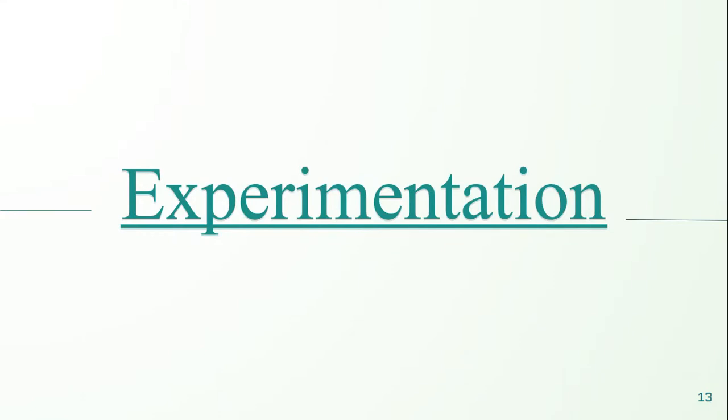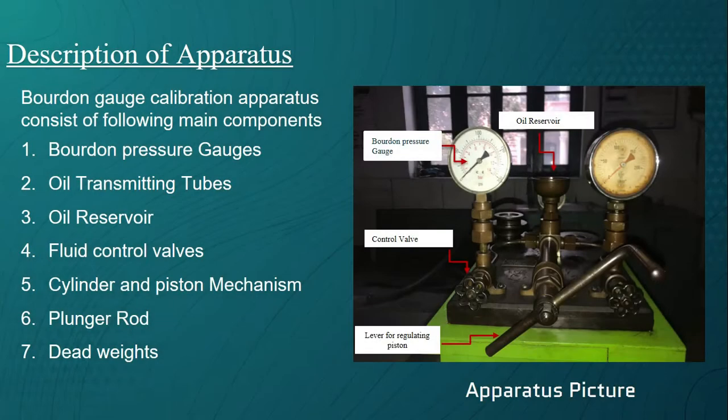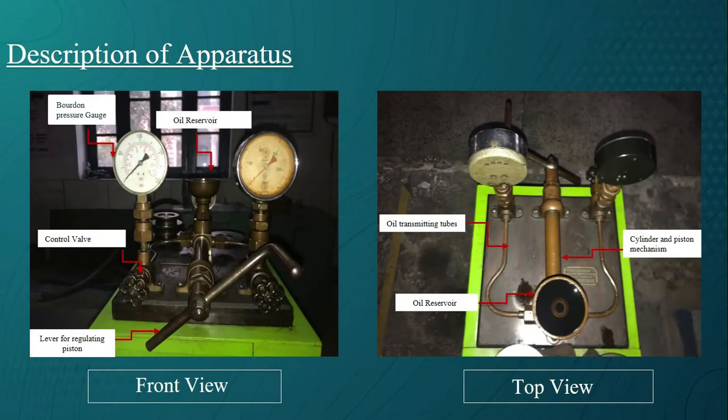Now we will move toward our experimentation section. This is our Bourdon gauge calibration unit. Bourdon gauge calibration apparatus consists of following main components: Bourdon pressure gauges, oil transmitting tubes, oil reservoir, fluid control valves, cylinder and piston mechanism, plunger rod and dead weights. The Bourdon gauges have two types of units displayed on dial for pressure measuring: one is in bar and other in pounds per inch square.